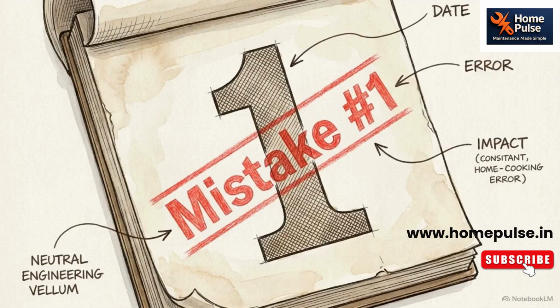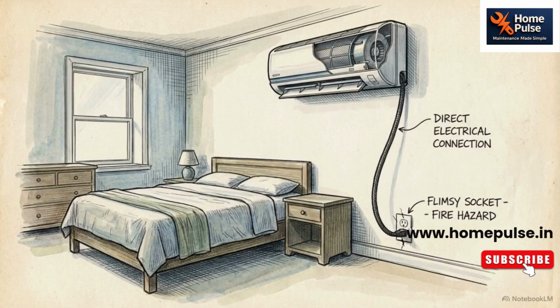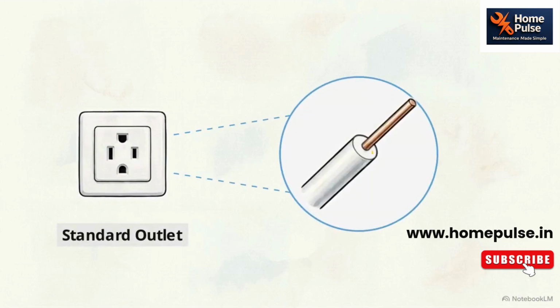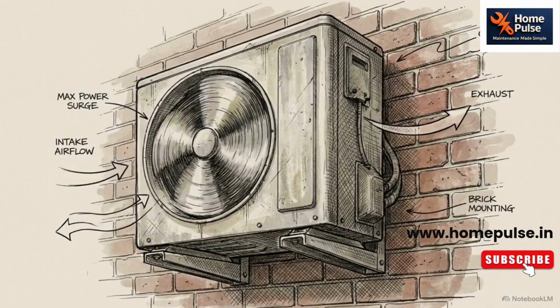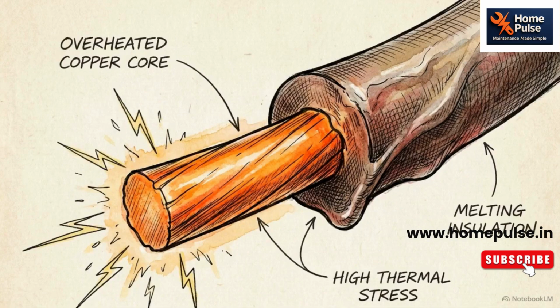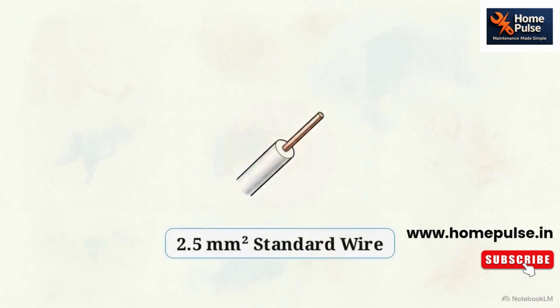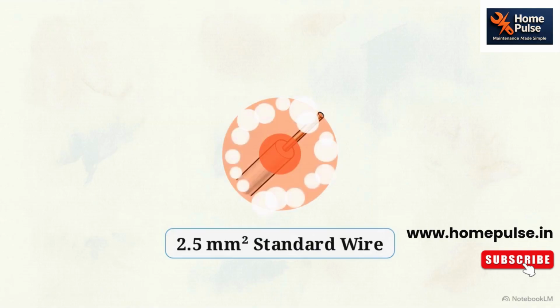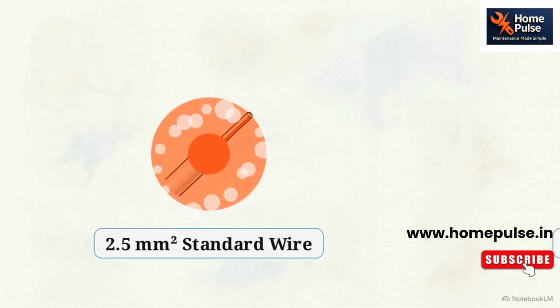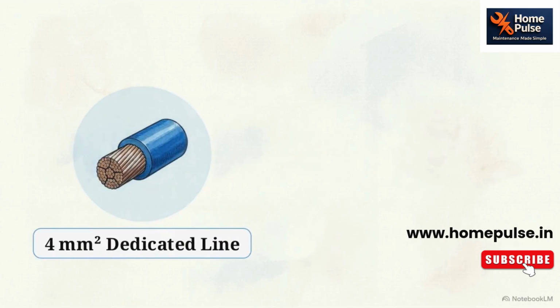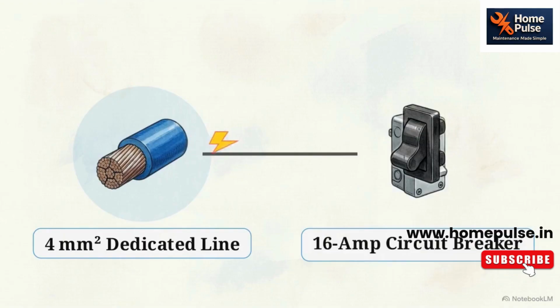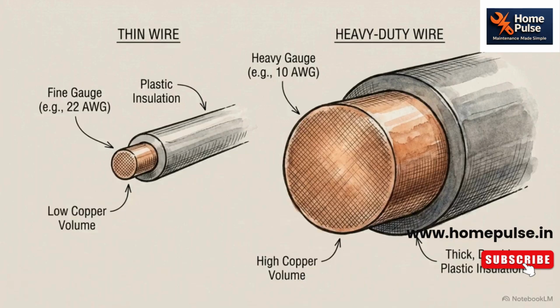The earliest mistake usually happens on day one, connecting a brand new AC directly into the existing shared electrical wiring of a bedroom. Standard room outlets use thin 2.5 square millimeter wiring. When a 1.5 ton AC cycles on, it draws a massive surge of power that these everyday wires simply aren't built to carry. Inside the walls, that thin wire heats up. The outer insulation bubbles and melts under the sustained electrical load. A safe baseline requires a dedicated 4 square millimeter copper wire paired directly with its own 16 amp circuit breaker. This brings us to the first trade-off. Saving a few hundred rupees on thinner installation wire drastically increases the probability of an in-wall electrical fire.